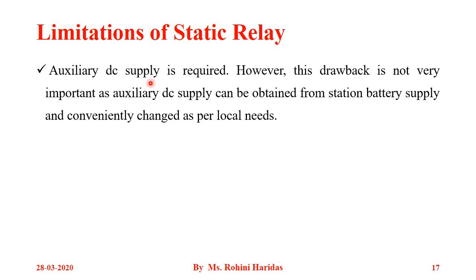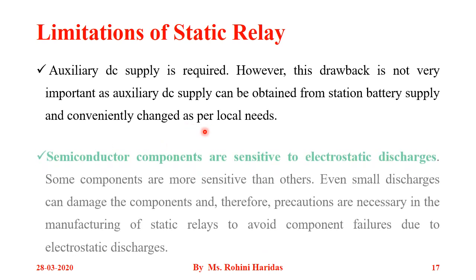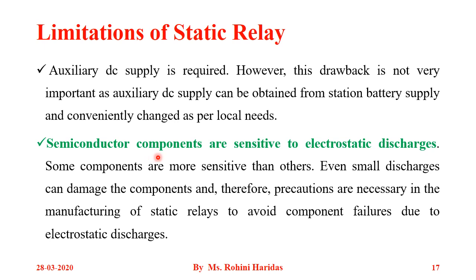Now let us see the limitations of the static relay. Auxiliary DC supply is required; however, this drawback is not very important as the auxiliary DC supply can be obtained from the substation battery supply and conveniently changed as per local needs. The semiconductor components are sensitive to electrostatic discharges — even a small discharge can damage the components, and therefore precautions are necessary in manufacturing static relays to avoid component failure.